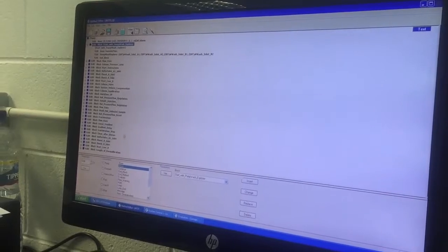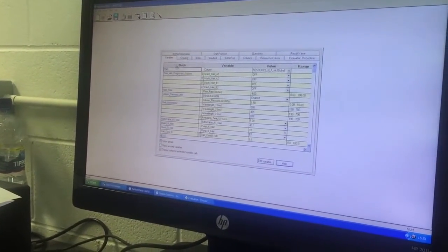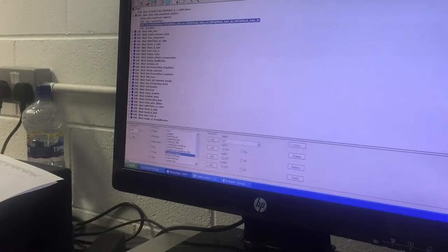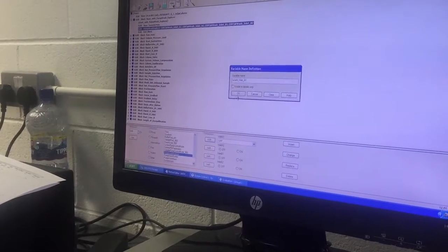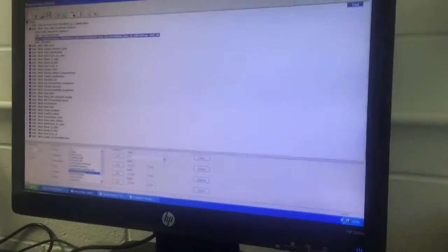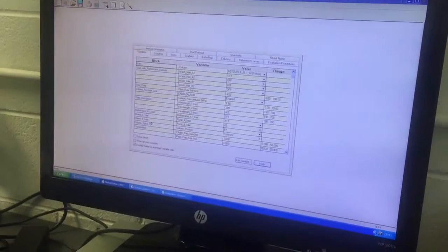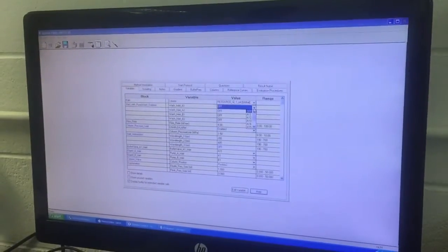That's an example. There's always this pump wash thing that's always off, and for the life of me, I don't know why. Every method starts with this, and it doesn't show it here. You have to go to show details to show it. Pump wash is part of the program, but I thought you could just do that before you even start your program. That's how we've been doing it. Yeah, it's in the manual: do it manually and then do the run. But every method you generate with this has a pump wash at the beginning, and for some obscure reason it's only available in details unless you manually change it.